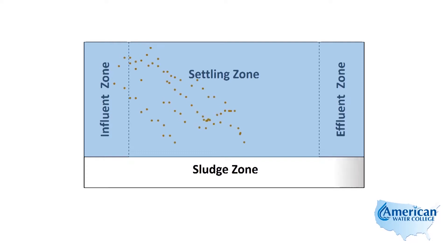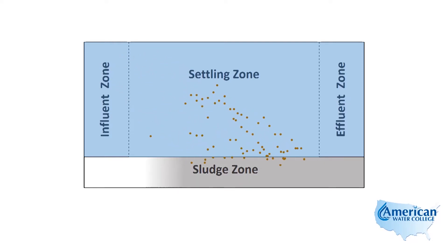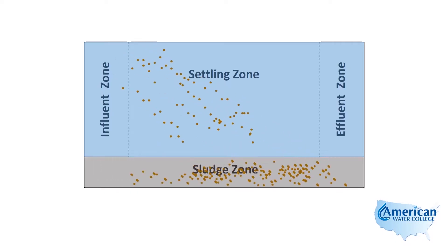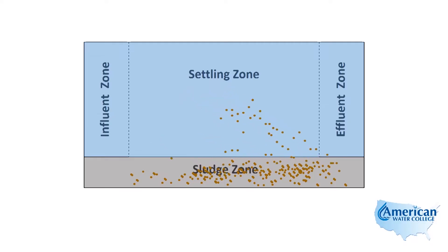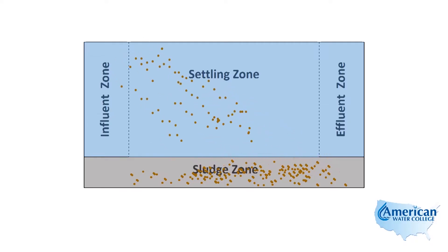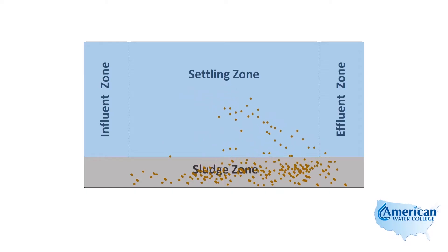On the bottom we have the sludge zone — this is where the settled solids collect. These are the four main zones of a conventional sedimentation basin, whether rectangular or circular: the influent zone, the settling zone, the effluent zone, and the sludge zone.